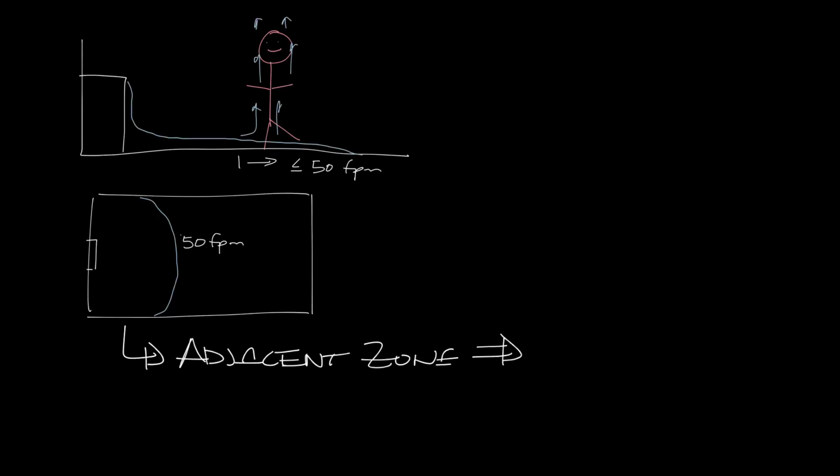This is very important, especially when you think about schools where a lot of displacement ventilation is being installed. You don't want the children sitting inside the clear zone where the velocity is too high and being cold all day. And you don't want the adjacent zone to be so big that you lose so much of your floor space where the kids can sit. But you also want to make sure that you are supplying enough air to the space.